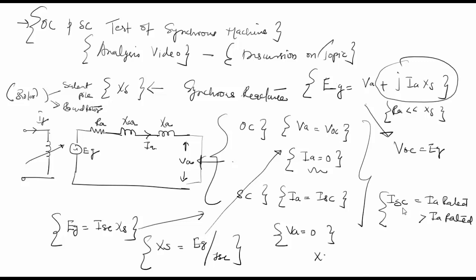So my XS can be given as VOC divided by ISC and this is for a field current which is equal to constant or a specific field current. This is how you can find your synchronous reactance based on the open circuit or the short circuit test.